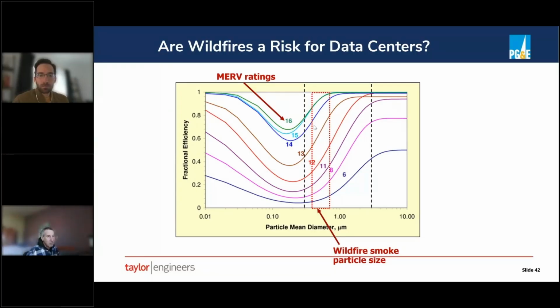We certainly worked on lots of data centers throughout California and elsewhere that use economizer only, and have not, as far as I'm aware, experienced any sort of failures related to wildfires. Also, if you have a data center that has mechanical cooling, you can typically shut off an economizer, right? If your mechanical cooling is sized to meet your whole load, you can use particulate monitoring, or you can just use manual control, your nose, or the news report. If there's a risk, you can simply manually override.